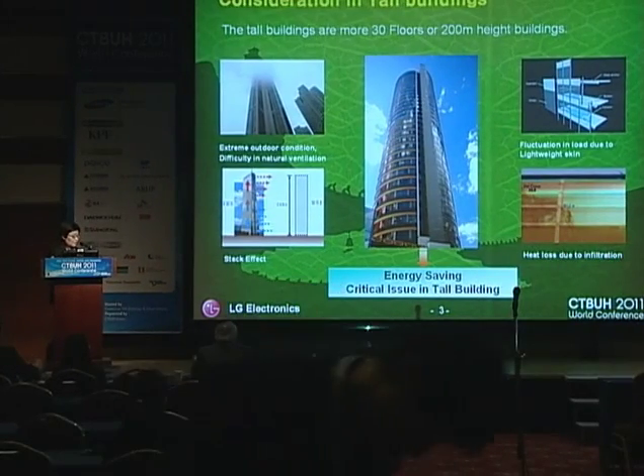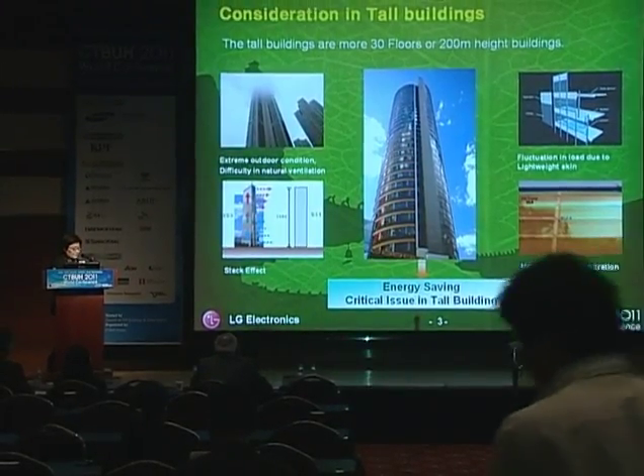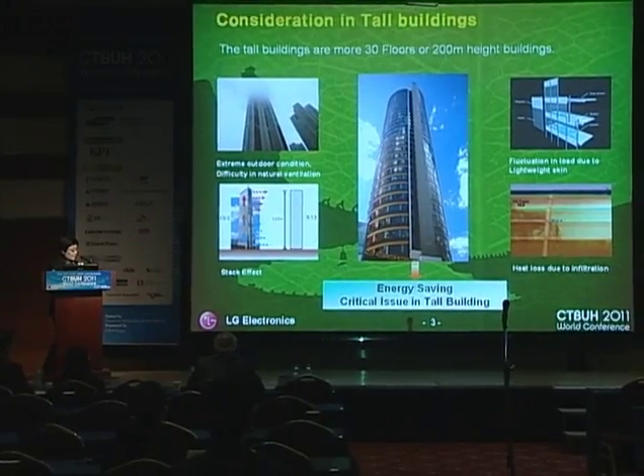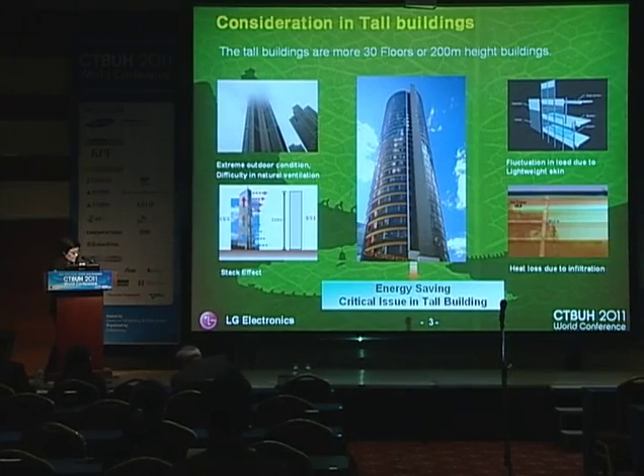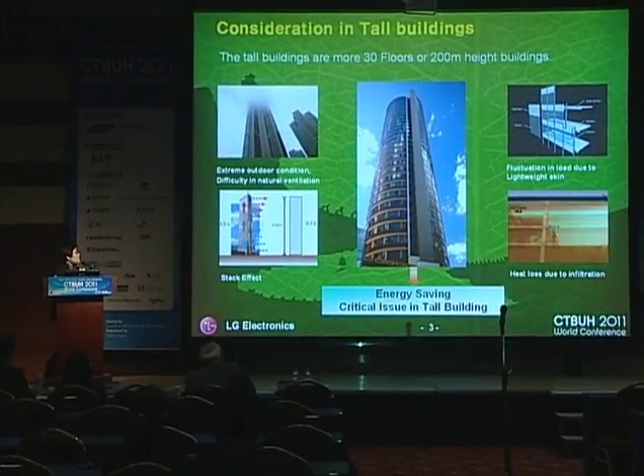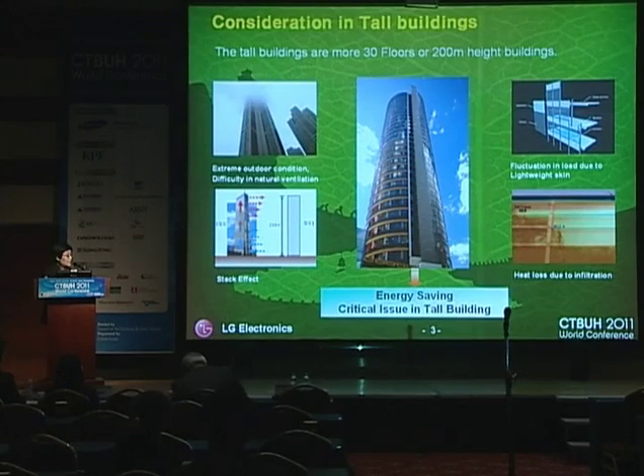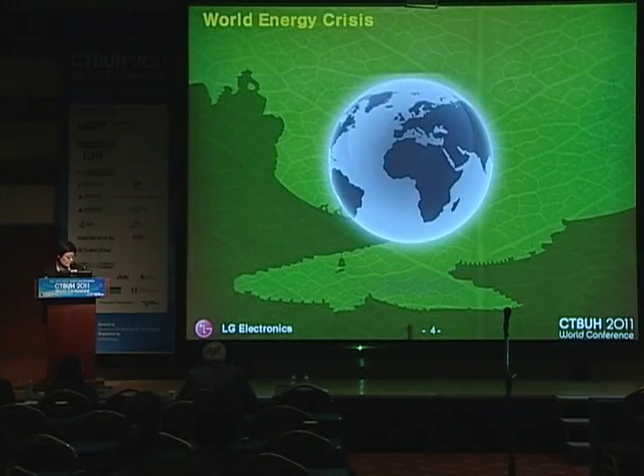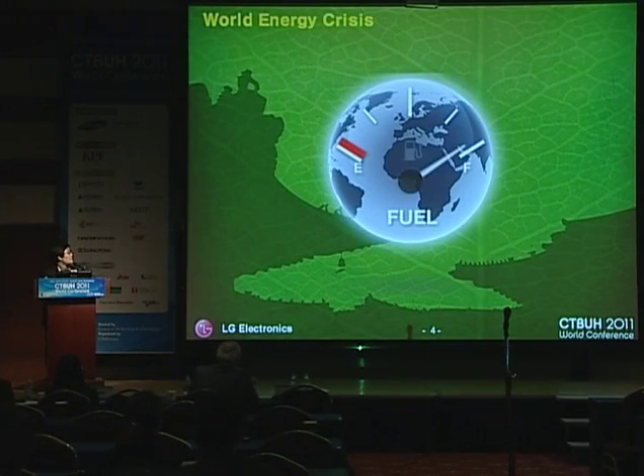Generally, a tall building is over the height of 200 meters, and 30 or 50 stories in Korea. A tall building has many energy and environmental problems. First, a tall building is not easy to ventilate because of air pressure drop and stack effect. Second, heat loss due to infiltration. Third, light construction materials are used, which affects the building load, so the building needs a lot of energy for heating and cooling. So these buildings need a more powerful and efficient air conditioning and ventilation system. So energy saving is a critical issue in tall buildings. Moreover, the world is facing an energy crisis due to depletion of fossil fuels. So energy saving is a very important problem.